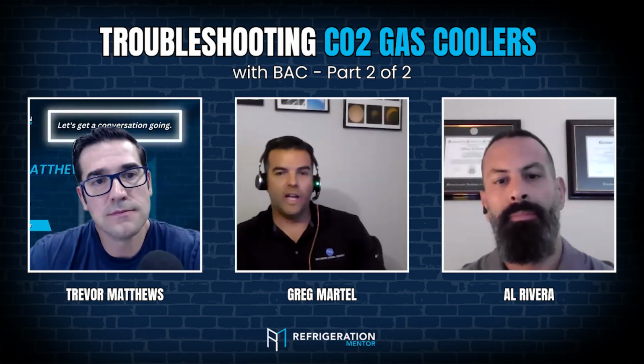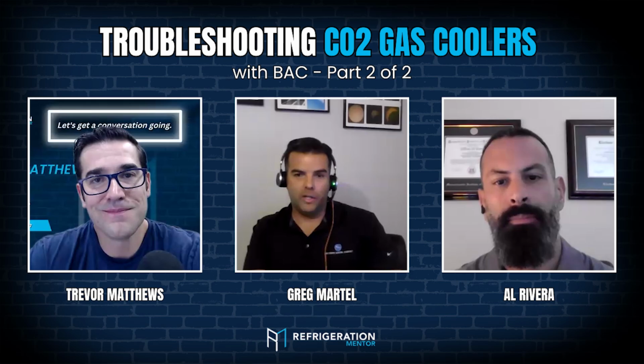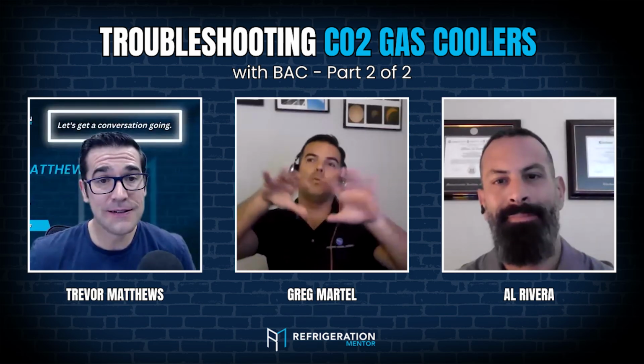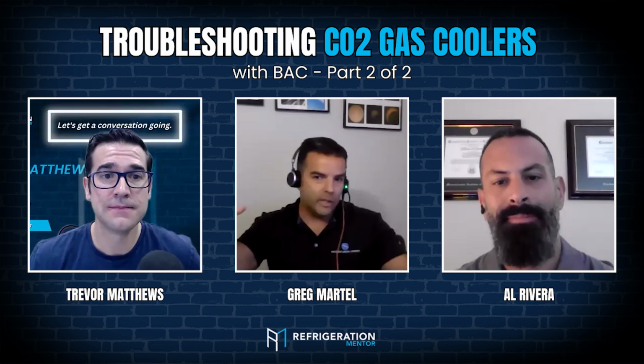What's another code? So another code that we get is called makeup water failure, no water in the system. So that is literally an alarm that our unit gets, and that one could be multiple things. So the first thing you should check is make sure that the pipe going to the unit has water. Just because the unit says that there's no water doesn't mean that there's no water in the state or in the building. You know what I mean? Like, you have to make sure that there's water in that pipe.